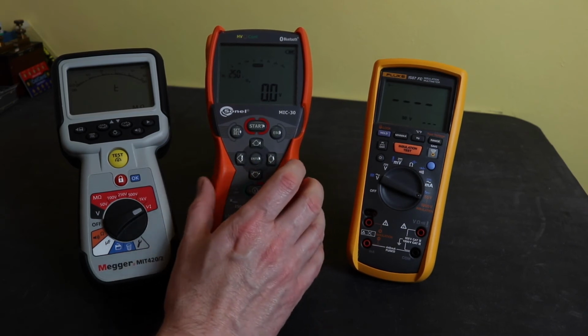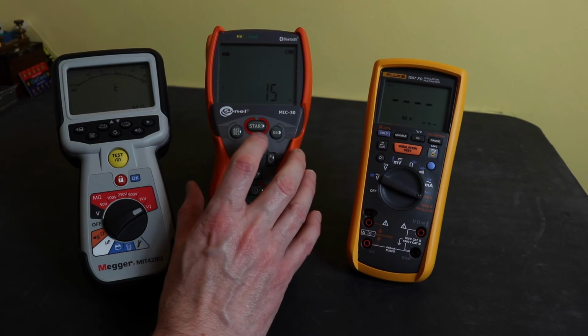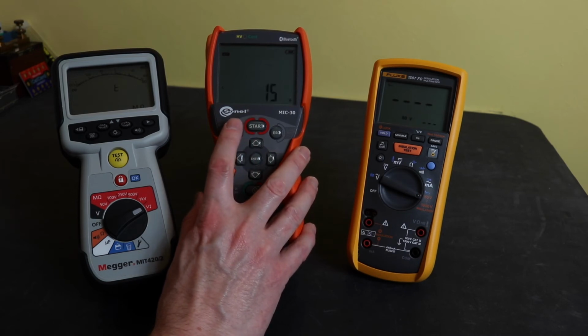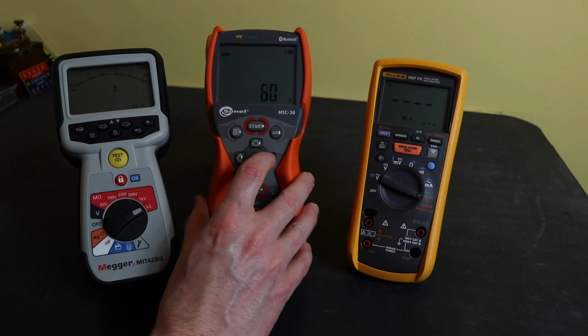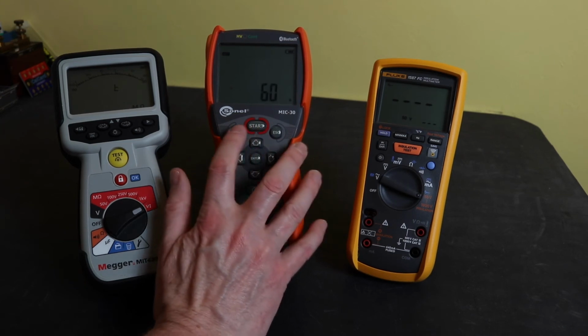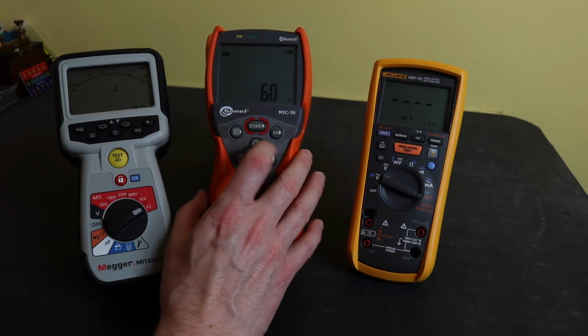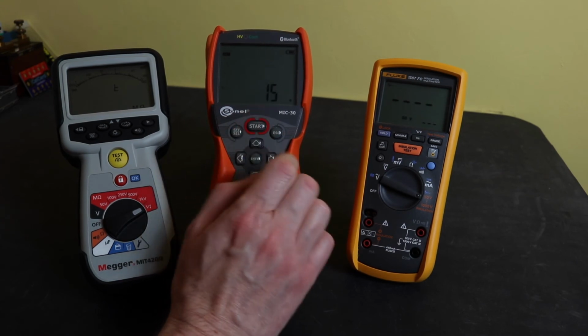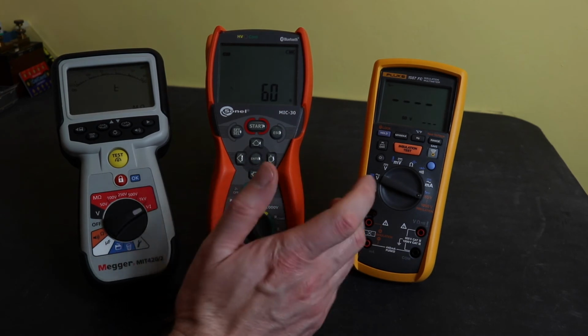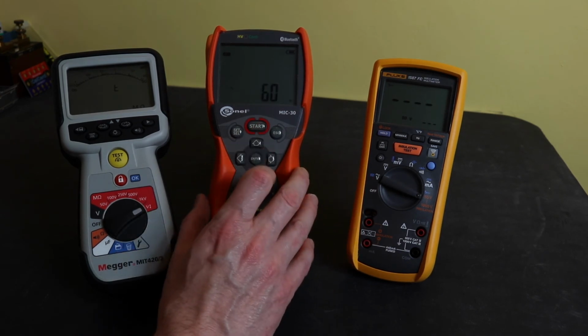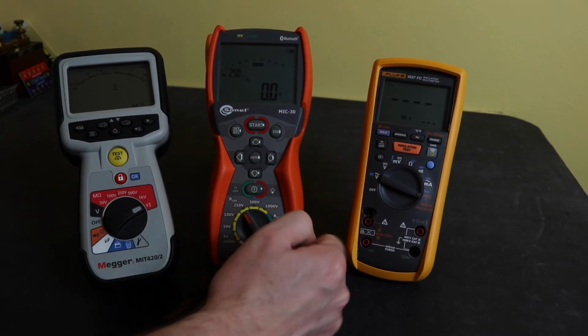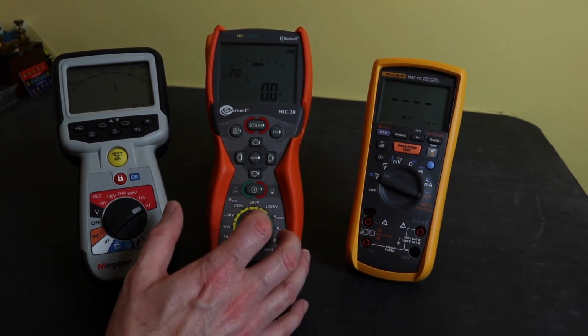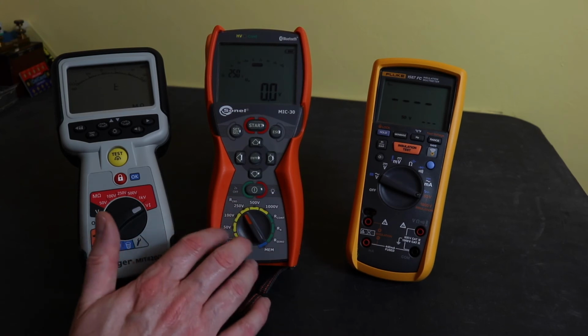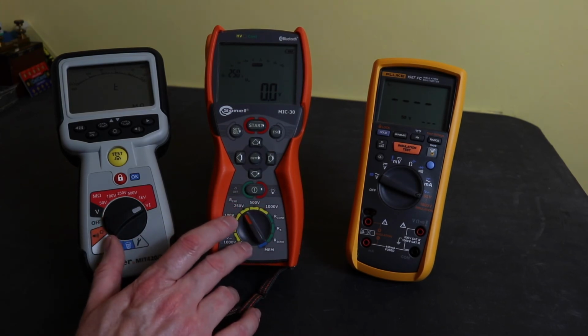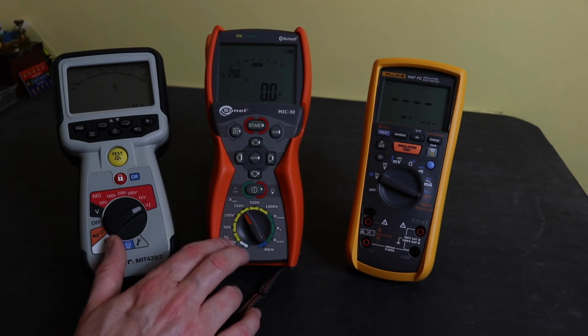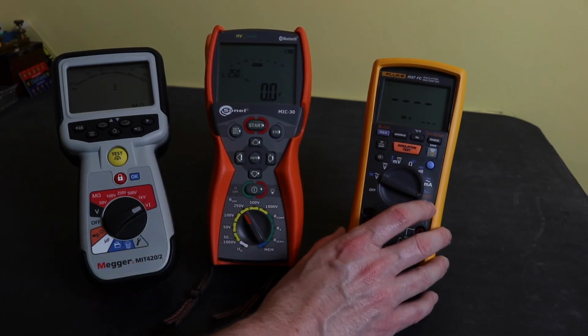Turn to 250. For the Sonel, you can set the times based upon a T1, a T2 and a T3, and it will then record the ratios. So it's currently set to 60 seconds, 30 and 15. If you change those up to the 600, you'll get the PI. On the 60 you get the DAR. So it is in there, it's just a slightly different way. During an insulation test, both the Megger and the Sonel will display either the current or the insulation resistance reading. You'll only get insulation resistance reading on the Fluke.